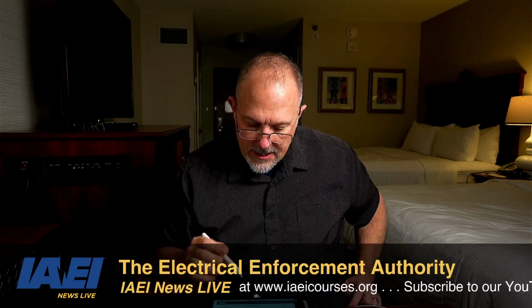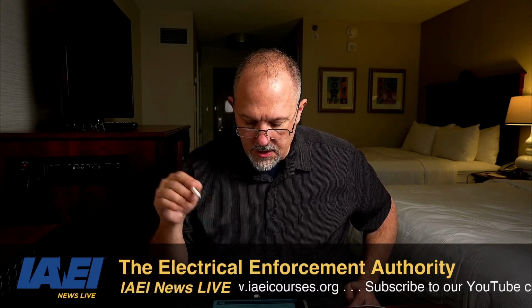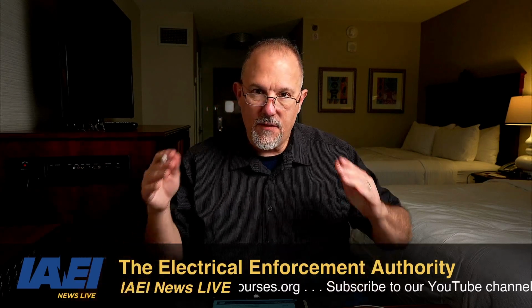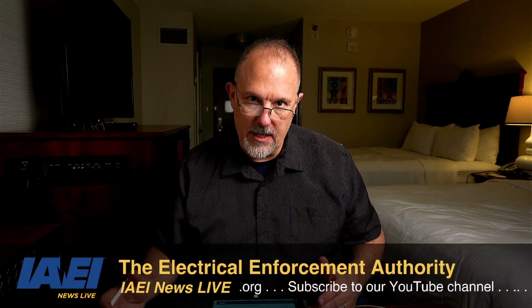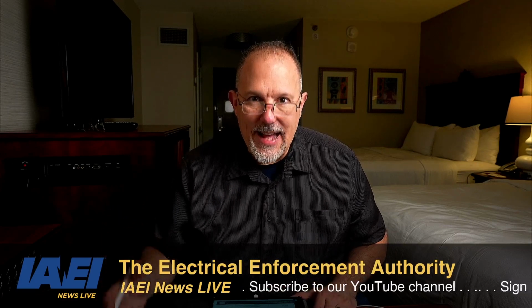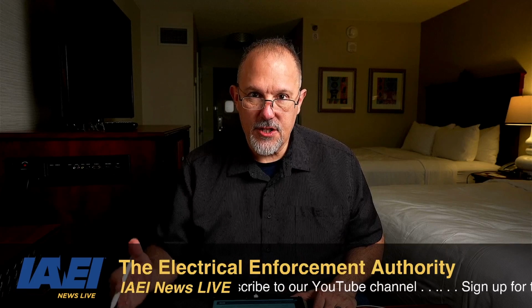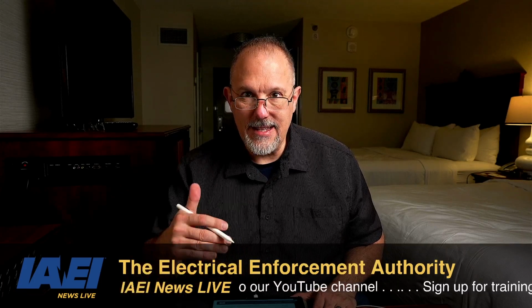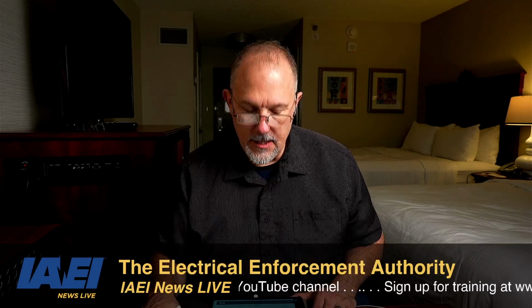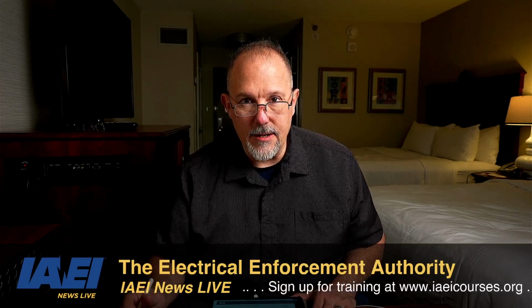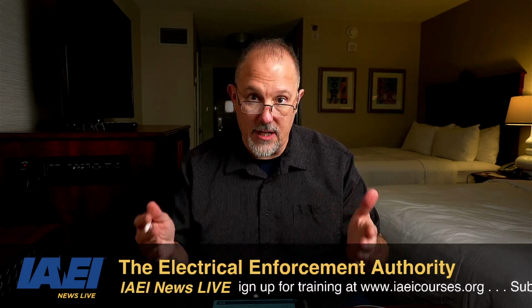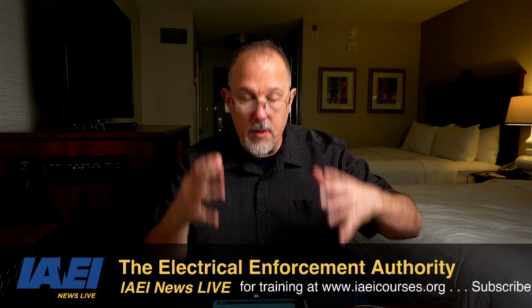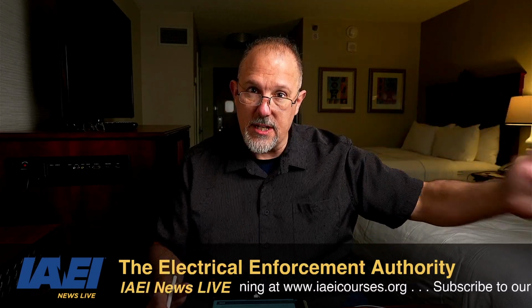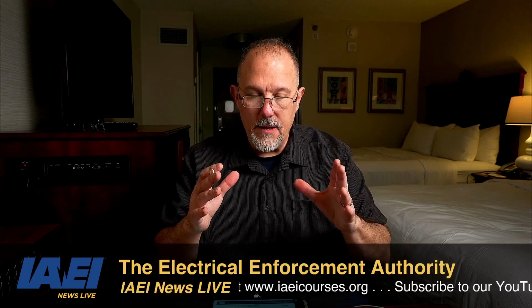Service conductors are the conductors from the service point to the service disconnecting means. So if I have a generator going to a transfer switch, that cannot be service conductors because the service point is not in that transfer switch. So those conductors from a generator are not service conductors, unless the transfer switch is listed as service equipment, and now the equipment is service equipment. But on the normal side, you're going to connect to the service point, right? So that's the transfer switch.